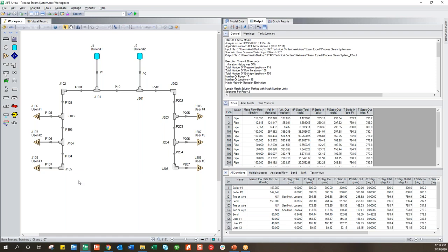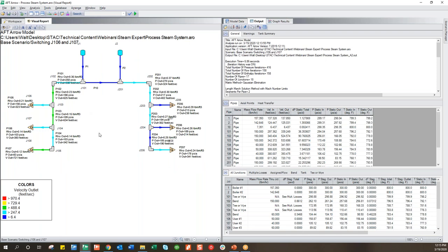That alone allowed me to stay within my operating points below 750 feet per second, again showing the complex nature of compressible flow. Little things like this, if you're in the design phase, making small tweaks can have a great impact on actual operation. The point is you're pulling off more flow before going through all of these extended pipes, so by the time it gets down there, it's a much lower velocity. You have less total pressure drop because you have less velocity — all of these things are coupled together. Looking at the visual report, everything is within reason, nothing above that alarming velocity.